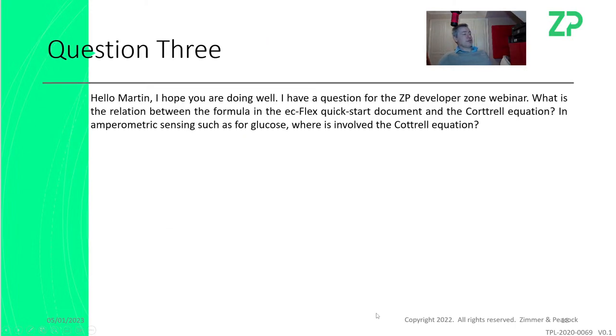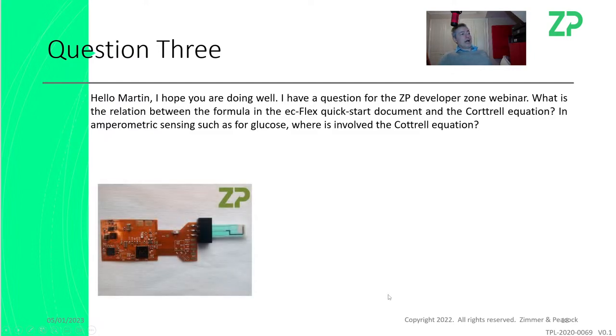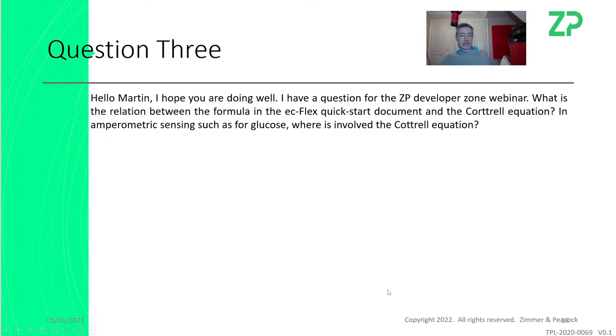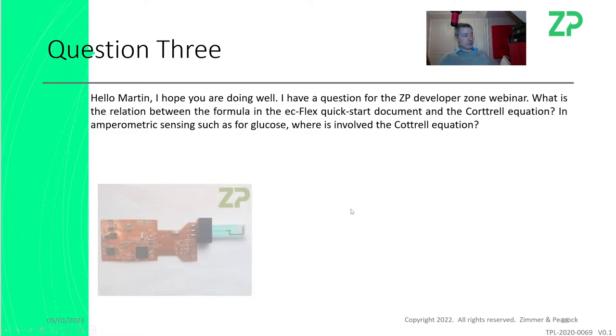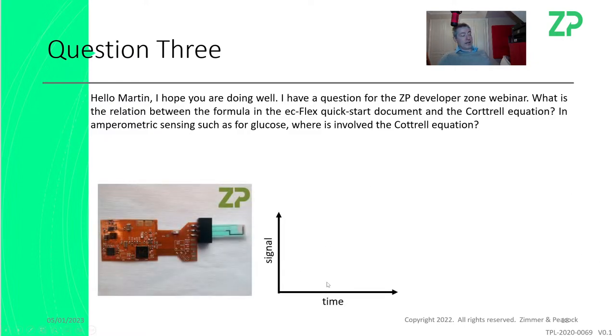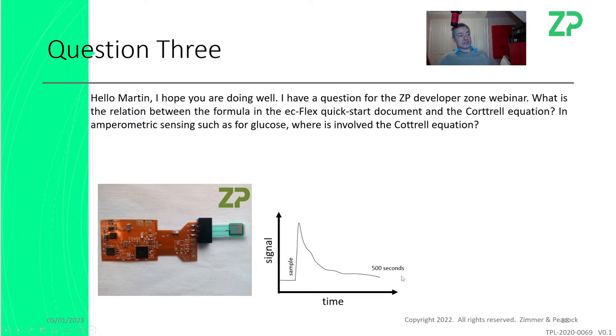Question three. The person has an ec-Flex and describes their signal as a Cottrell-type response. I suspect the signal type they have is: sample goes on, the signal jumps up, but it's not stable — it's falling with time. So they have signal versus time. I've put 500 seconds here because if we're doing a CGM — continuous glucose monitoring — sensor, we often find the signal isn't settled until about 500 seconds.